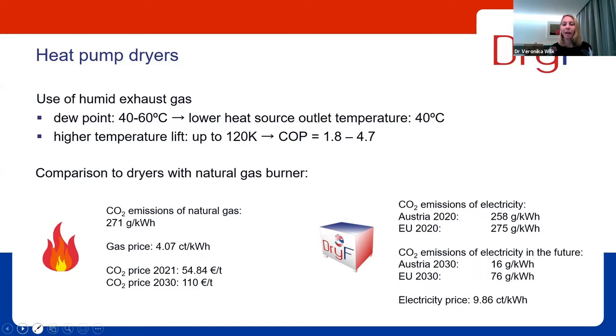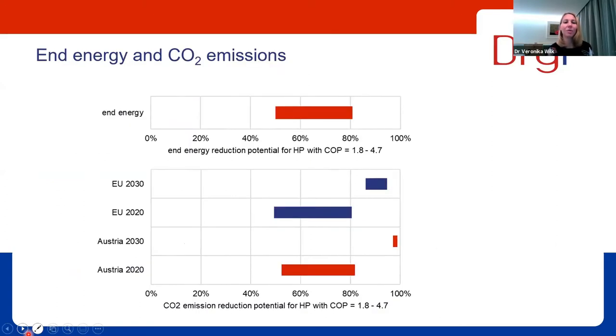And in Austria, we have ambitious goals for 2030. We want to have all our electricity supplied from renewable energy carriers. And by then, the use of 1 kilowatt hour of electricity will lead to 16 grams of CO2 emissions. So this is a very low value. The European average is expected to be a bit higher, but also considerably less than we have today. So if we put in all these values, we come to this result in terms of end energy and CO2 emissions. To read this diagram, at the lower end we have the result for a COP of 1.8, for the high lift application. And this is the result for the COP of 4.7 for the low lift application.